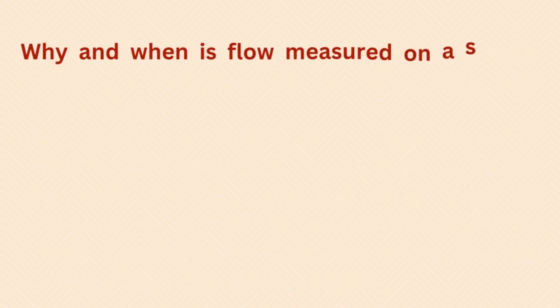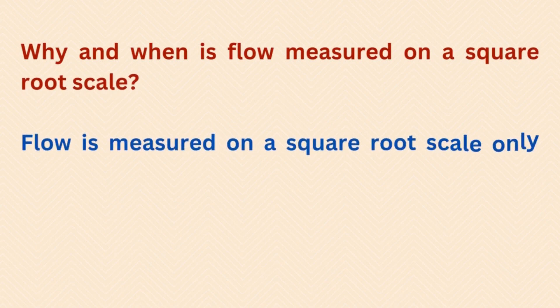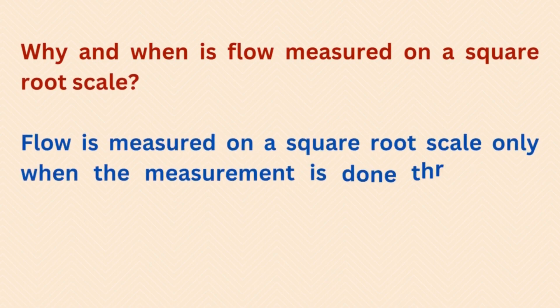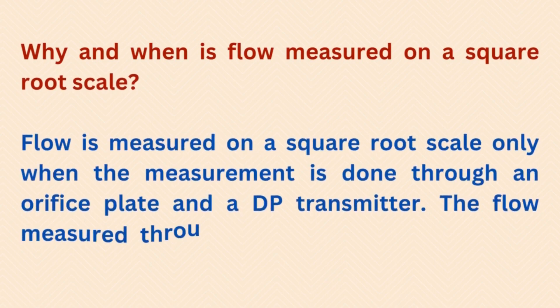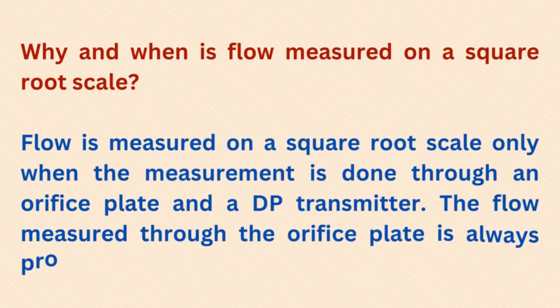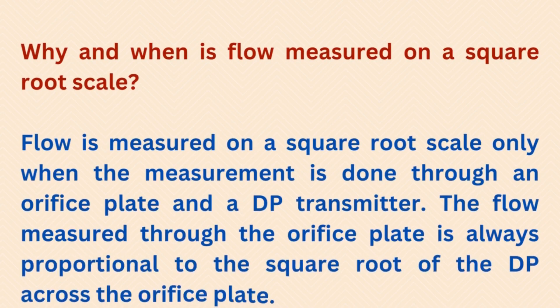Why and when is flow measured on a square root scale? Flow is measured on a square root scale only when the measurement is done through an orifice plate and a DP transmitter. The flow measured through the orifice plate is always proportional to the square root of the DP across the orifice plate.